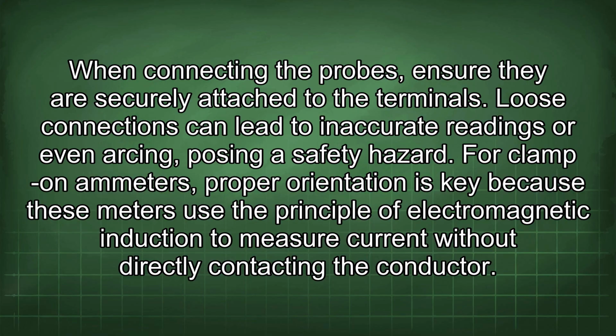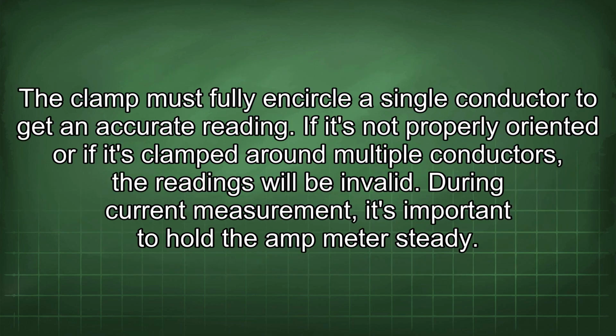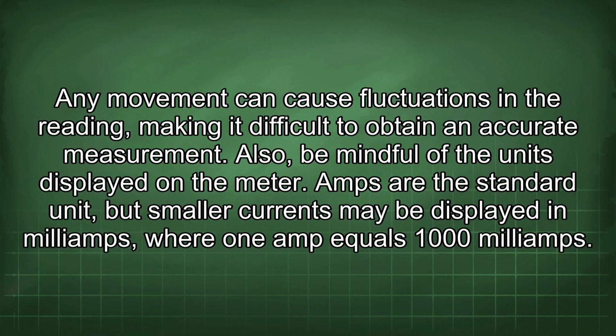For clamp-on ammeters, proper orientation is key because these meters use the principle of electromagnetic induction to measure current without directly contacting the conductor. The clamp must fully encircle a single conductor to get an accurate reading. If it's not properly oriented or if it's clamped around multiple conductors, the readings will be invalid. During current measurement, it's important to hold the amp meter steady. Any movement can cause fluctuations in the reading, making it difficult to obtain an accurate measurement.